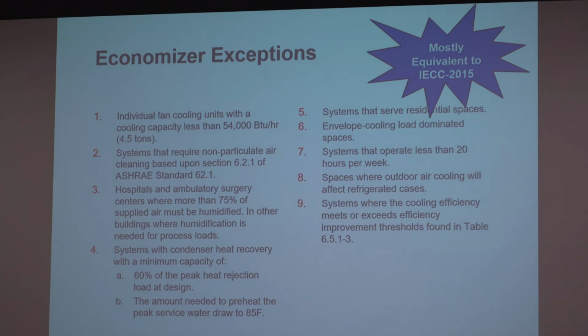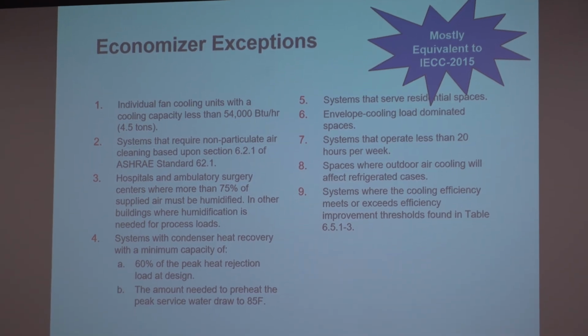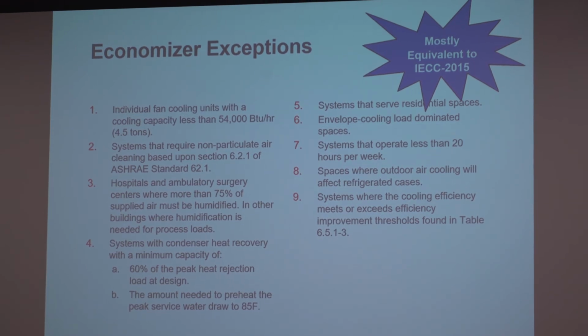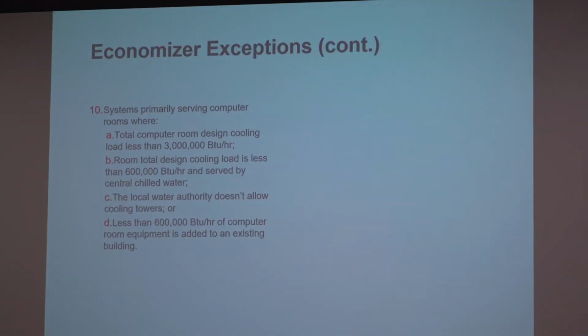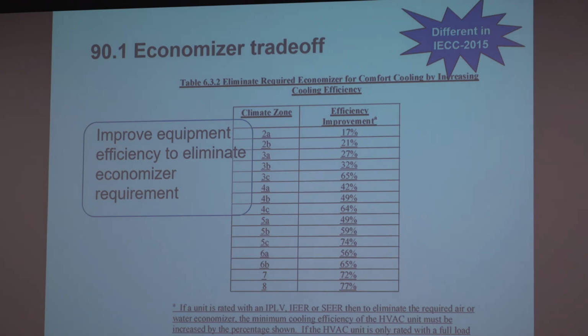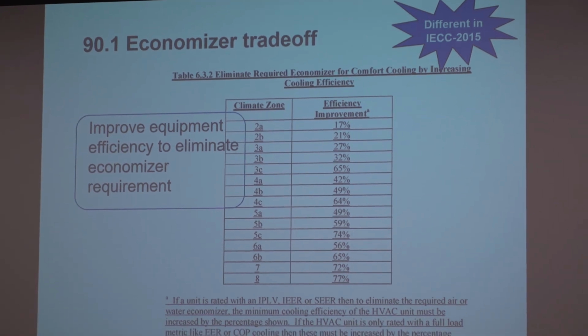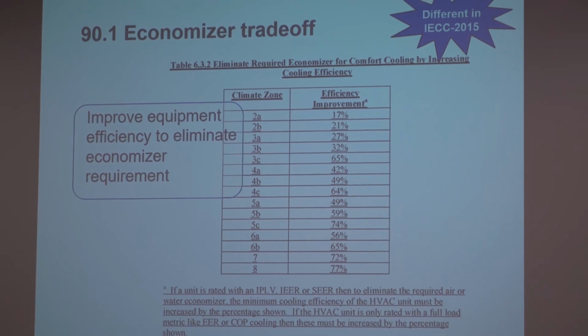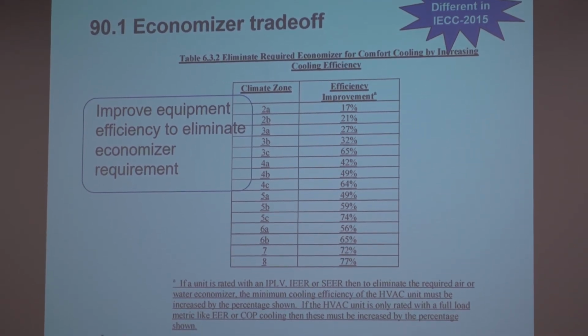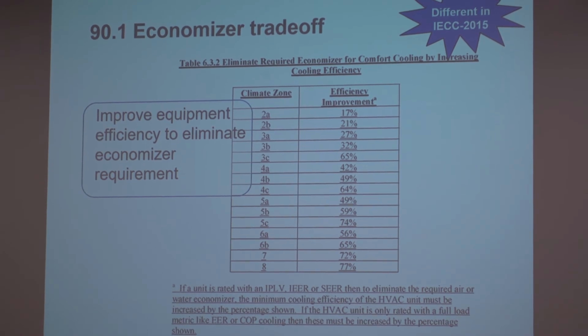Here are the exceptions. The one that seems to be used the most is number 1, but that's going away in IECC because of the aggregation clause. That's pretty much it. Computer rooms have a little bit different exception, and it's not in the IECC version. So here's the efficiency trade-off table that's in 90.1, and it's the same table in the 2013 and the 2016 versions. So if you were in climate zone 4 and you were able to get 42% better on the part load metric versus the table value, then you can use this to get out of having to have an economizer.